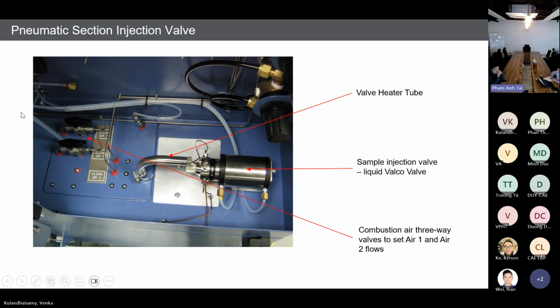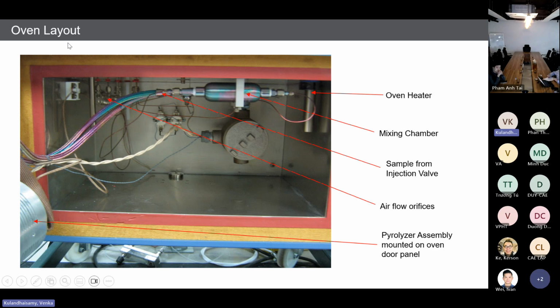Okay. So on the side of the pneumatic valve, you can see the injection valve. This is the sample injection valve. The sample injection valve will get the sample from the SCS and then inject 1 microliter of sample to the pyrolyzer. Okay. Yeah, this is the oven layout. I told you about the mixing chamber, right? Yeah, this is the mixing chamber.